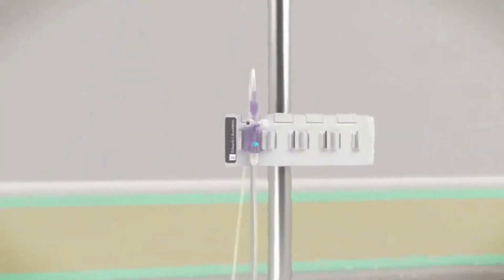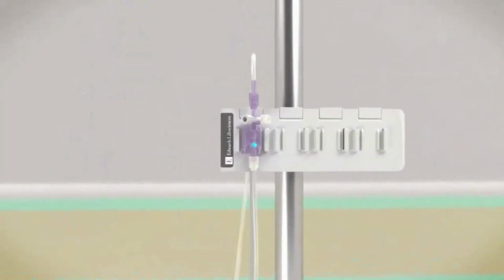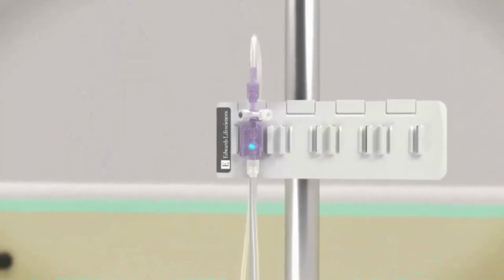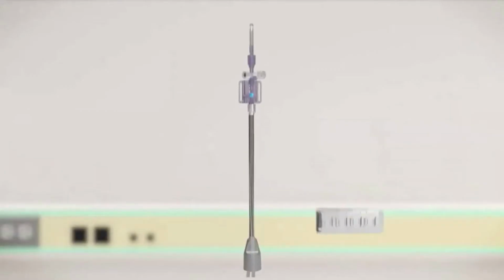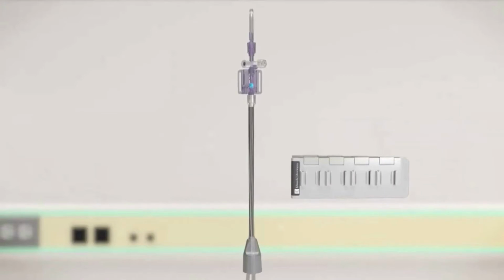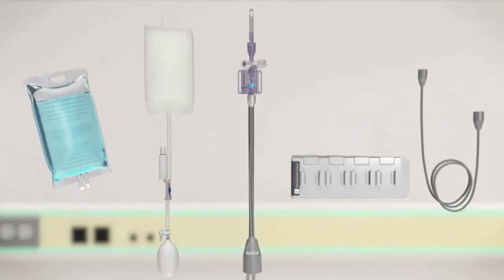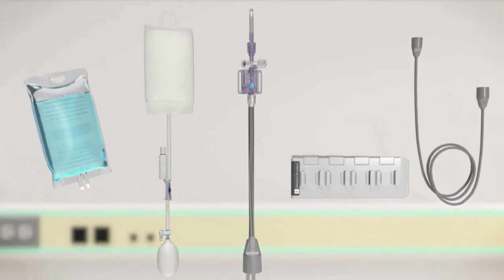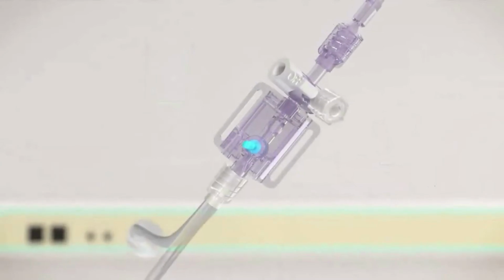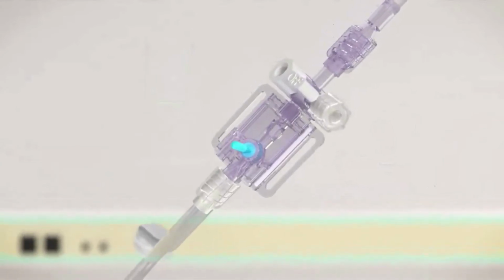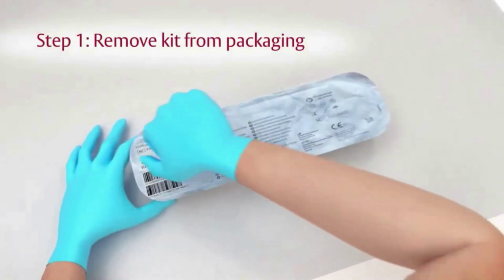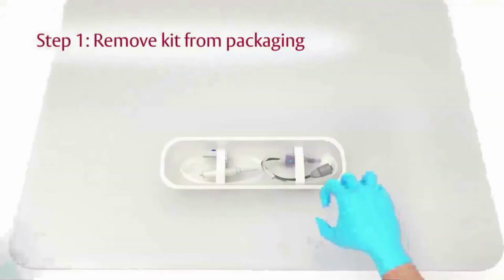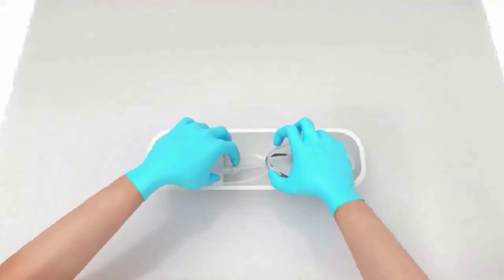The following animation demonstrates best practice in the setup of a single TruWave disposable pressure transducer. Here's what you will need to get started. One TruClip holder or an arm mount strip, a 500 or 1000 milliliter normal saline IV bag, a properly sized IV bag pressure cuff, and appropriate cable that connects your bedside patient monitor to the TruWave transducer. Prepare the TruWave transducer using the following 5 steps. Step 1. Using aseptic technique, remove the transducer kit from the sterile packaging and ensure all connections are secure.